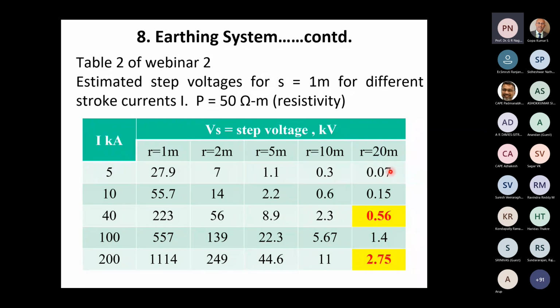I will repeat it. If you have a ring conductor bonding all the down conductors at the ground end, the building being 20 meters by 40 meters, the perimeter is 120 meters. If we equate it to a hemisphere of radius 20 meters, the step voltages are given by this. This is a very illustrative example. It is not far from the truth, but not exact. That's all I can say, but pretty close to real life.